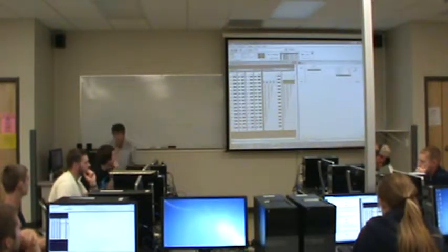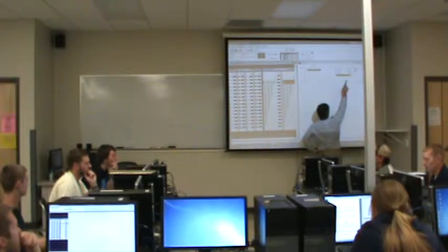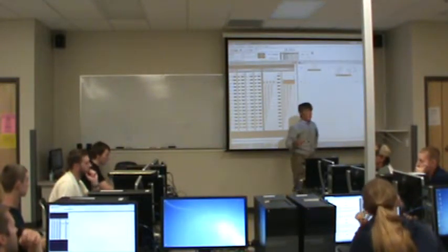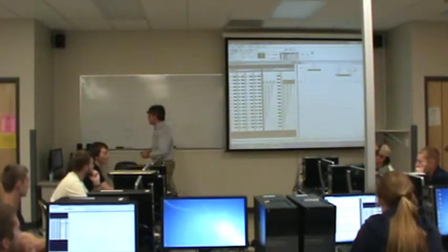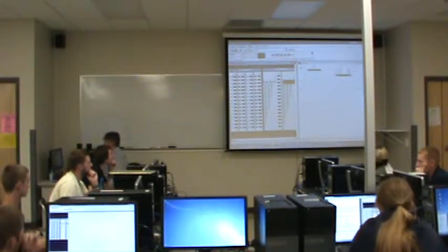Now, over here is a CU, that stands for count up bit, and all CU is, is the bit associated with this counter that goes true whenever the rung preceding it is true. Now that's handy because sometimes you want something to be triggered when the counter is triggered, and you can use the count up bit to make that happen. I'm going to modify the program again, and I'm going to make a light come on whenever the count up is detecting a low to high transition.